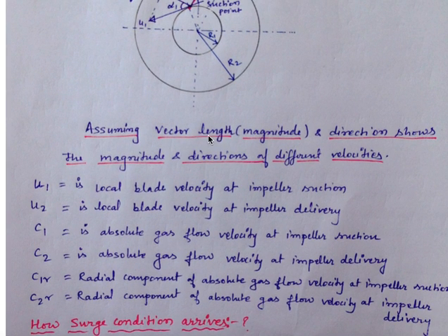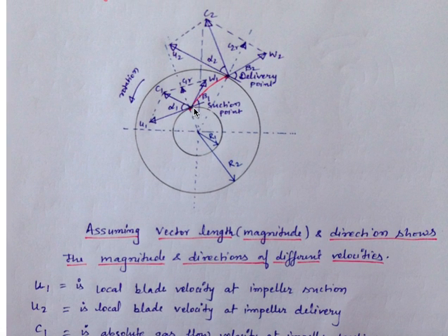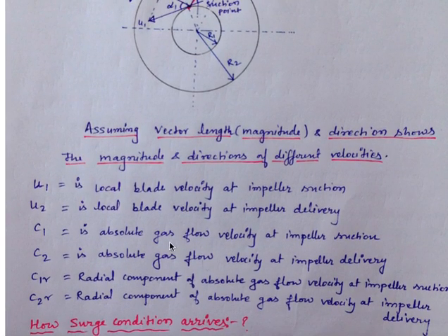The vector length represents its magnitude and direction — the length and direction of each vector shows the velocity of the impeller and the absolute gas velocity at the suction and delivery points. A longer vector means higher velocity magnitude; a shorter vector means lower velocity. At the suction point the vectors are shown smaller because the gas velocity and impeller velocity are lower. At the delivery point, due to centrifugal action, velocity increases, so those vectors are shown bigger.